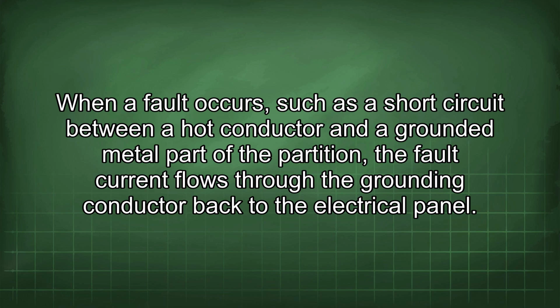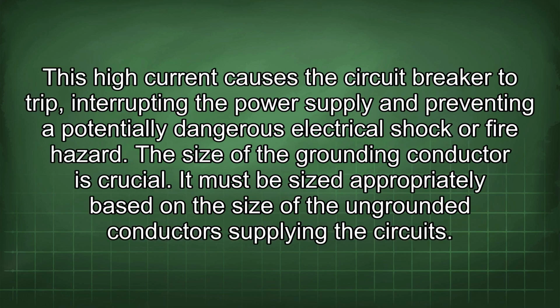When a fault occurs, such as a short circuit between a hot conductor and a grounded metal part of the partition, the fault current flows through the grounding conductor back to the electrical panel. This high current causes the circuit breaker to trip, interrupting the power supply and preventing a potentially dangerous electrical shock or fire hazard. The size of the grounding conductor is crucial. It must be sized appropriately based on the size of the ungrounded conductors supplying the circuits.